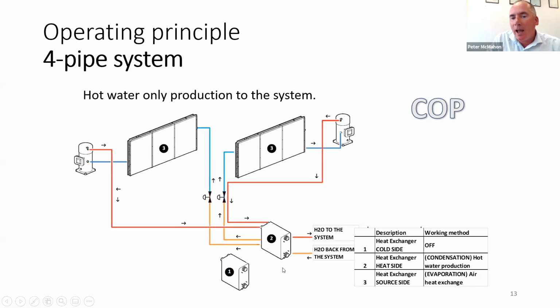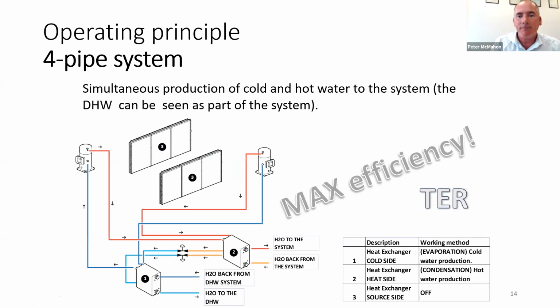Now, let's say we have 400 kilowatts of heating. We still have the same input power for argument's sake. This can vary, but I'm keeping it very simplistic here. So let's say we have our same input power of 100 kilowatts. And again, the terminology coefficient of performance is really just what you get out versus what you put in. So let's say we have 400 kilowatts of heating capacity, 100 kilowatts of input power, your COP is 4. Very straightforward. Now, this is really where the benefit is.